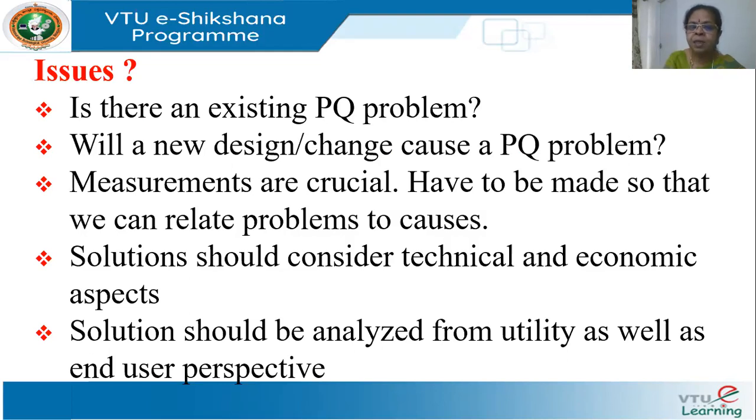So my solution should include inverter plus filter, because the filters are necessary to mitigate the harmonic problem, which may not have been there in your original system, but which your solution is going to create. So this is actually very complex. Okay, it's very intricate. And that is where your modeling and all that will help to see whether the introduction of these mitigating equipment will cause fresh problems. So this is the second issue to be addressed whenever you want to have an evaluation procedure.